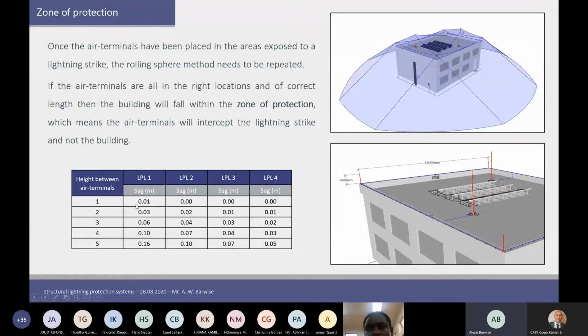So here we can see, as an example, if the height of the air terminals is, for example, 4 meters, and we are dealing with lightning level 1, that the sag will be 0.1 meters. What that means is we have to select our terminals such that the sag is less than the actual terminal's height, to ensure that we're not exposing the building. We are in fact ensuring that we are striking the terminals.